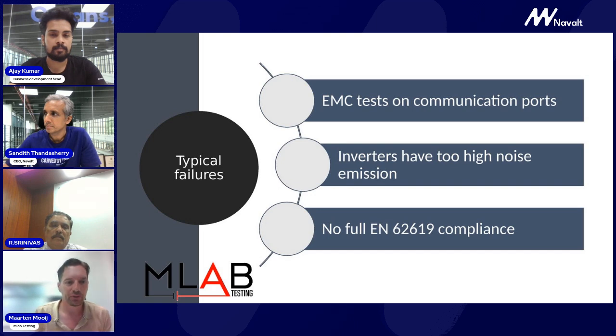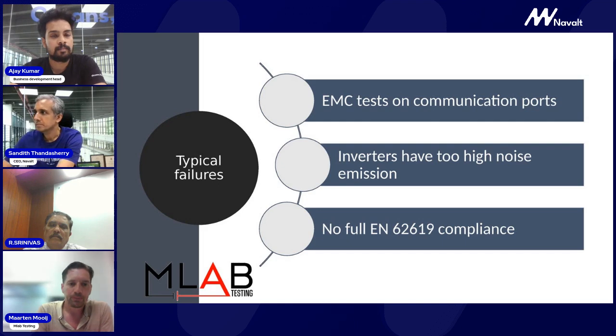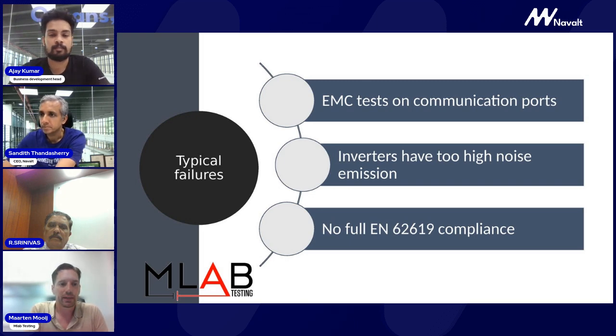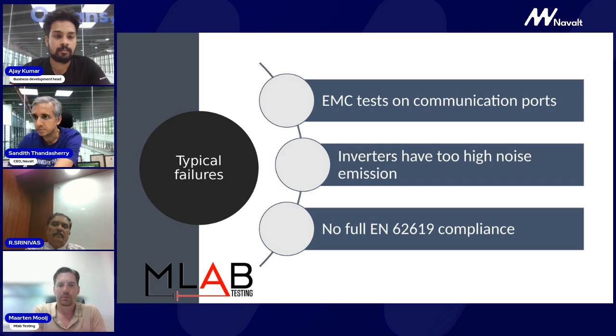What are the typical failures that we see? So most products, they will fail on the EMC tests and mainly on the communication ports. Because the terminals, the plus and the minus, yes, that's easy, big cables, and they are connected directly to the cells, and the BMS is not really very influenced by disturbances based on these cables coming in. The problem is that the communication ports usually use a CAN connection, which is very low voltage. So you can imagine what happens if you disturb higher voltage levels on CAN communication. So usually the communication fails.